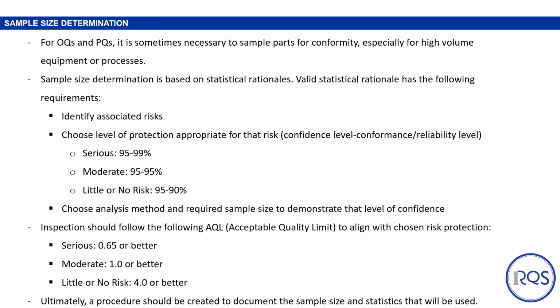For OQs and PQs, it is sometimes necessary to sample parts for conformity, especially for high-volume equipment or processes. Sample size determination is based on statistical rationales. Valid statistical rationale has the following requirements: the identification of associated risks, the appropriate protection level, and that's the confidence level or conformance level and the reliability level. So for things that are deemed serious, that's 95 to 99% confidence; for moderate, it's 95, 95; and for little or no risk, it might be 95, 90. And then also you need to choose the analysis method and required sample size to demonstrate that level of confidence.